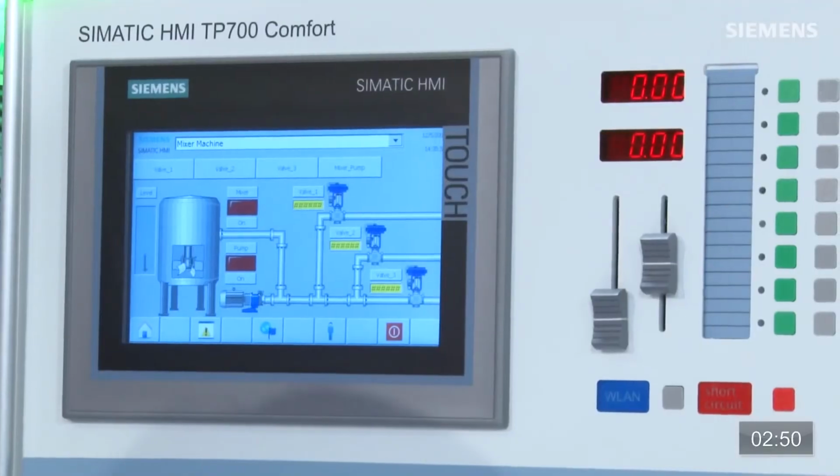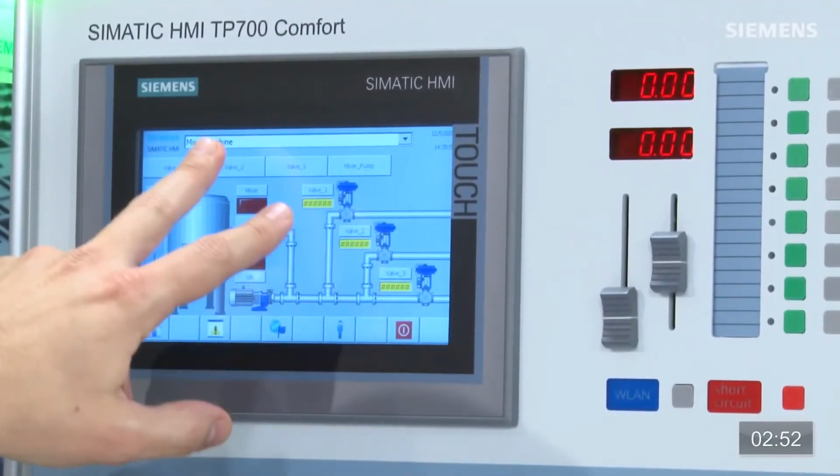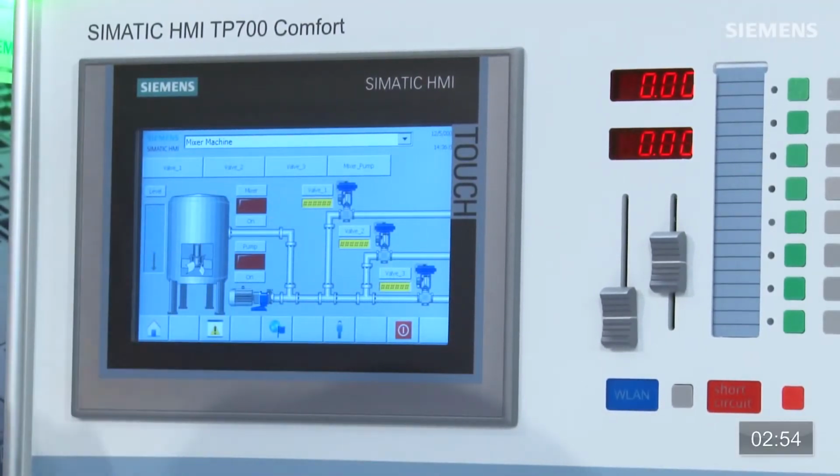However, in our new system, as it starts to power up, you'll see immediately that we actually have hash marks across the valves, so they're not receiving any communication. The level doesn't work either. And here in a few seconds, it's going to go into a stop mode, and it has.